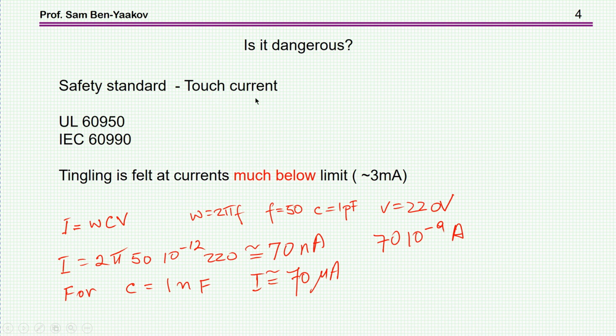Touch current is the current that flows into your body when you touch the metal part of the casing. There are two standards, UL and IEC, and they talk about a limit of 3 milliamps. That is a maximum of 3 milliamps allowed when you touch an electrical appliance or a laptop.